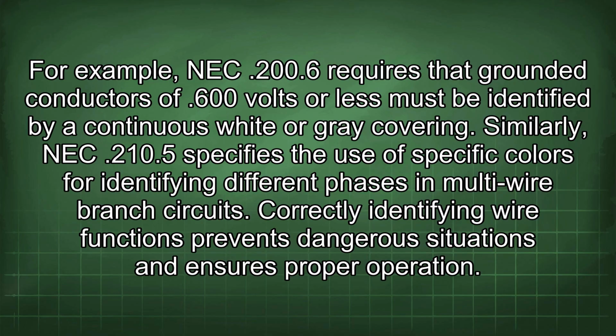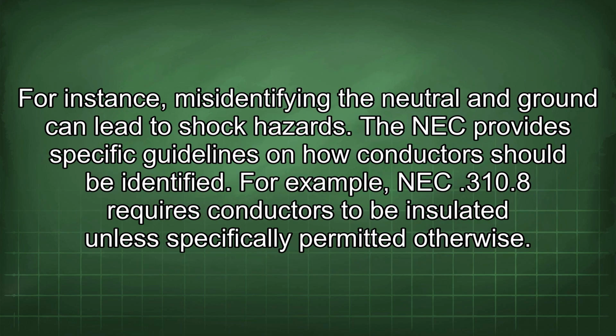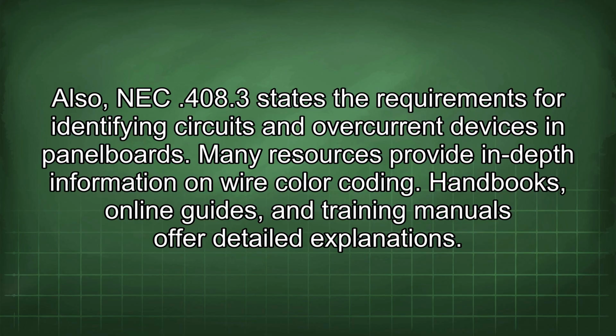Correctly identifying wire functions prevents dangerous situations and ensures proper operation. For instance, misidentifying the neutral and ground can lead to shock hazards. The NEC provides specific guidelines on how conductors should be identified. For example, NEC 310.8 requires conductors to be insulated unless specifically permitted otherwise. Also, NEC 408.3 states the requirements for identifying circuits and overcurrent devices in panel boards.